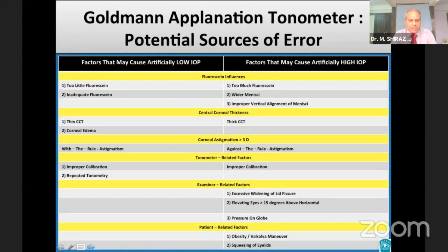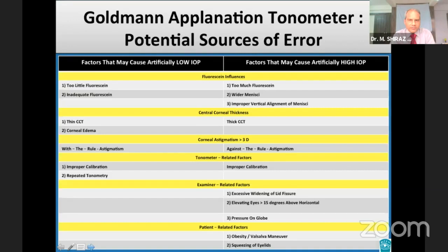Factors such as central corneal thickness, corneal biomechanical factors, inappropriate amounts of fluorescein dye, pressure applied on the eyelids, Valsalva maneuver, breath holding, and high astigmatism can all affect the accuracy of measurements taken with the GAT.